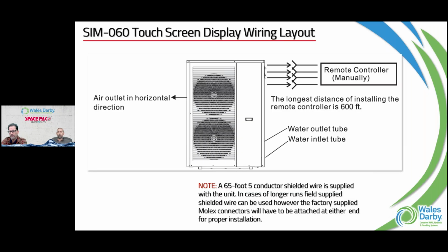It does come with a touchscreen display. It is a controller, so technically it does not need to be on the system for it to operate, right? We can monitor some things there, program some stuff within the unit. It does not need to be there to operate. So we give you a 65-foot conductor. It's a 5-wire shielded wire. So if you needed to extend it, we could go up to 600 feet away. So you think, again, putting that thing remote in the woods or something like that and be able to get it back into the house. Now we can mount that controller in a mechanical room or something like that.